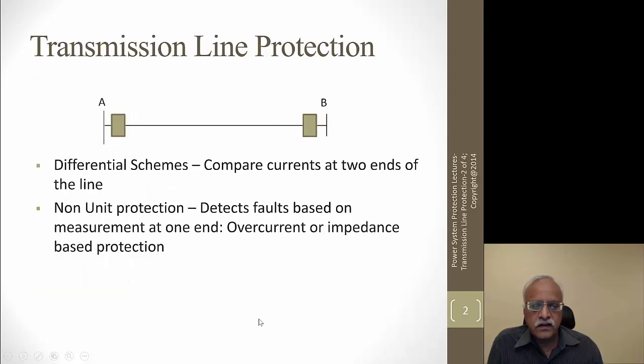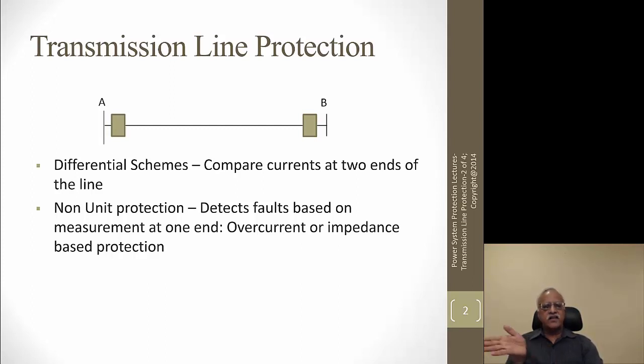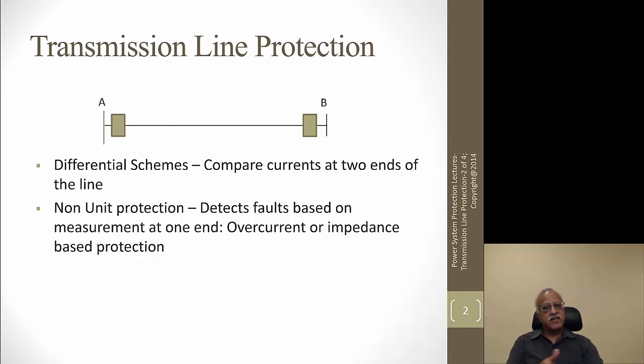There are other current-based schemes called non-unit protections. Instead of exchanging information between two ends like a differential scheme, here we look at the magnitude of the current going in. If there is a short circuit, the current increases and you can make a decision based on that. In an interconnected network, you can look at the direction and magnitude of the phase current — these are called directional overcurrent relays.